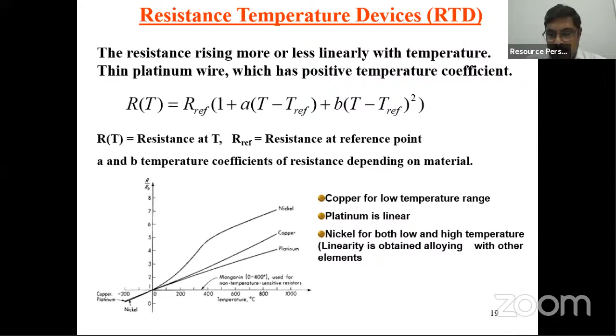Of course, instead of platinum, one can also use nickel. Usually the RTD is a PT100. The platinum will have a resistance of 100 ohm at 0 degrees, that's why it's called a PT100. We can also use copper or nickel, or any metal. If you take platinum, it has very linear characteristics anywhere between -200 degrees Celsius and up to about 1000 degrees Celsius, so it's more suitable. Copper has some kind of linearity issue. And nickel, you see here, has a different slope.